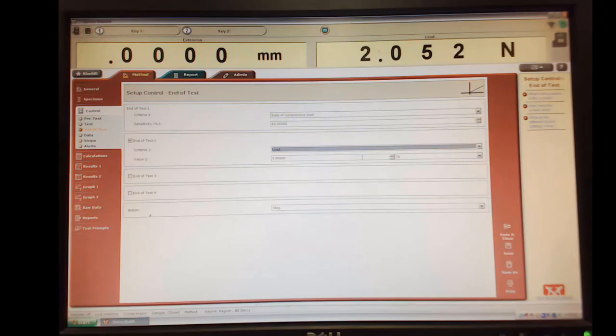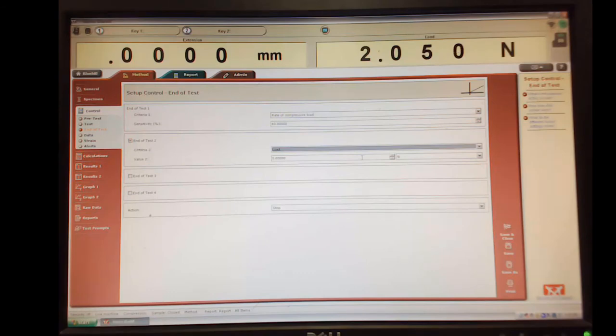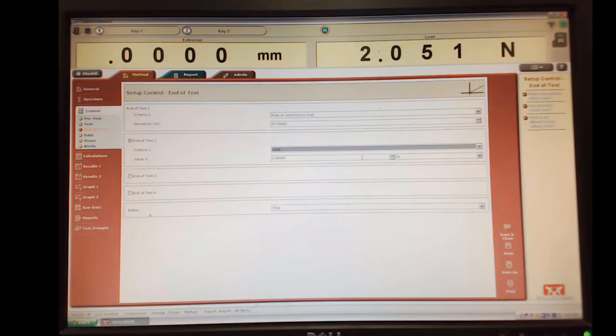All right, so I'm going to put load. Again, we want to protect the load cell with this load. So if you remember, in the tension testing, the load cell was rated to 100 newtons. So we wanted to stop it at 80 newtons.